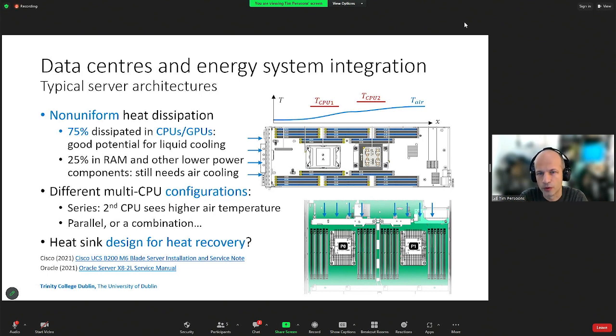In a so-called hybrid air-liquid cooling scenario, what we typically mean is that the CPUs would be liquid cooled, and the memory modules and all the rest of the components would still be air cooled. If you follow the airflow through the system, the air flows from left to right, pushed by chassis fans through the system. The air will gradually pick up heat as the air travels through the server. And so locally, you will see a slightly different temperature in the first CPU and in the second CPU.